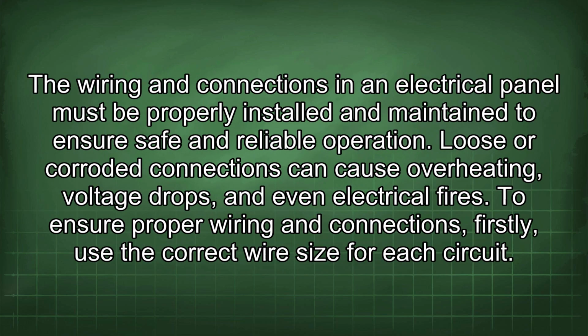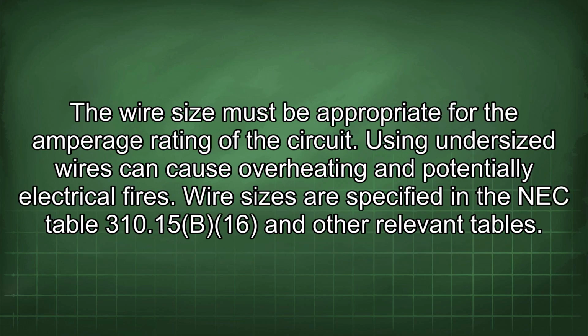The wiring and connections in an electrical panel must be properly installed and maintained to ensure safe and reliable operation. Loose or corroded connections can cause overheating, voltage drops, and even electrical fires. To ensure proper wiring and connections, firstly, use the correct wire size for each circuit. The wire size must be appropriate for the amperage rating of the circuit. Using undersized wires can cause overheating and potentially electrical fires. Wire sizes are specified in the NEC Table 310.15(B)(16) and other relevant tables.